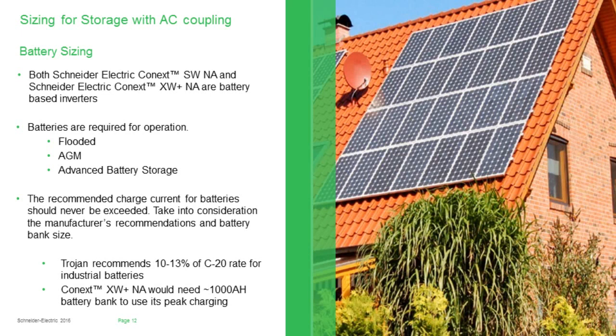So now that we have a system, we know that we need to have storage inside of there, what do we recommend for actually that relationship or that ratio? And we have to take into account not only the charging capacity of the inverters themselves, meaning we can't put 16 kW of solar onto a 6.8 kW battery-based inverter. That will literally overwhelm the inverter's capacity. As an example for Trojan, of course, they recommend 10 to 13% of the C20 rate for industrial batteries, meaning that really we're looking at a charge rate of about 5 hours to properly charge those batteries. And with the XW Plus, of course, we would need almost 1,000 amp hour battery bank to use its peak charging.